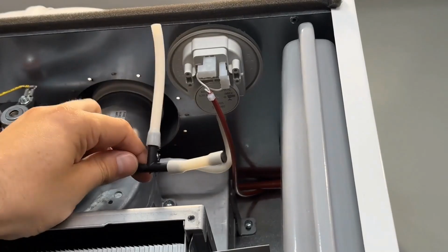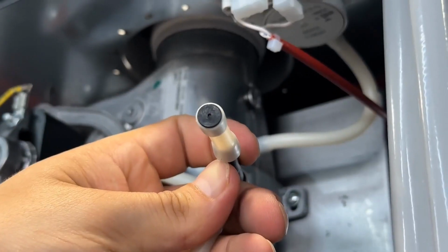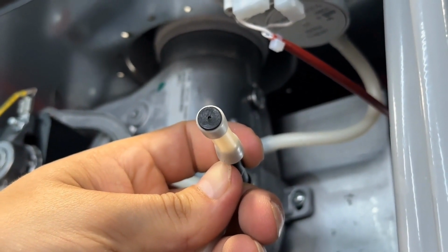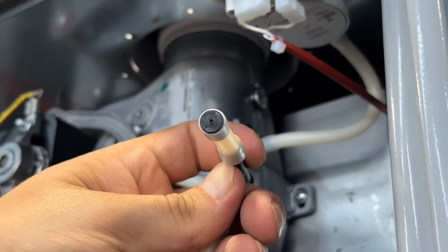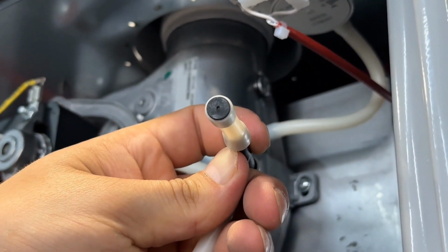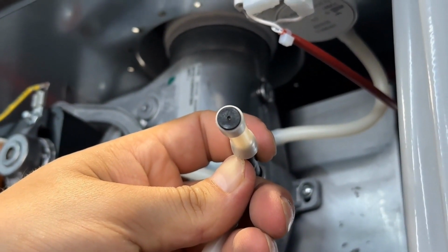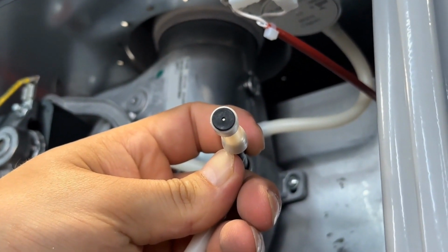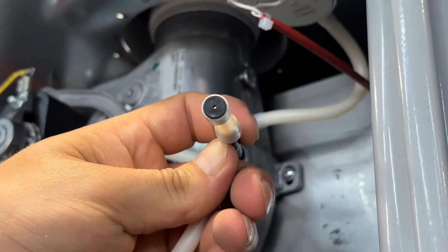In our boilers, we have upgraded this system. The connection to the pressure switch is made through a T with purge valve. Since the pressure switch operates on a vacuum, dry air is constantly blown through the boiler casing, which prevents the formation of condensate. And if condensate does get into the tube, it will be blown out because there is an air intake. So, what can you do yourself if condensate still forms?